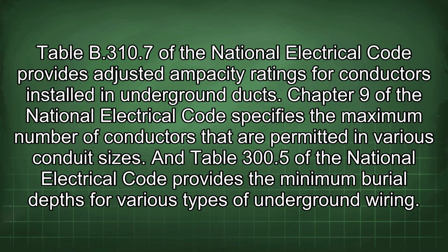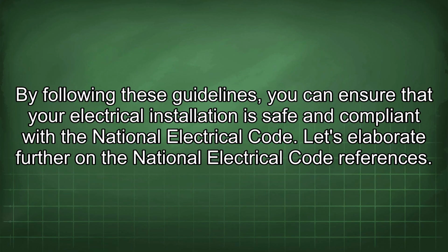Table B.310.7 of the National Electrical Code provides adjusted ampacity ratings for conductors installed in underground ducts. Chapter 9 of the National Electrical Code specifies the maximum number of conductors that are permitted in various conduit sizes. And Table 300.5 of the National Electrical Code provides the minimum burial depths for various types of underground wiring. By following these guidelines, you can ensure that your electrical installation is safe and compliant with the National Electrical Code.